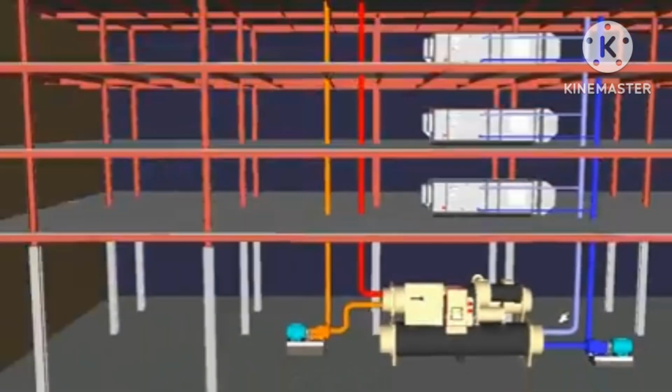Also in this instance we've got one plant item, and by plant item I mean a mechanical asset. In the real world it's unlikely you'll have just one. You'll probably have n plus 1, so n, whatever you need, you have that number plus 1, because if this item here was to break, or say this pump here was to break, then we wouldn't be able to produce cooled water or condenser water, and we wouldn't be able to cool the building down.